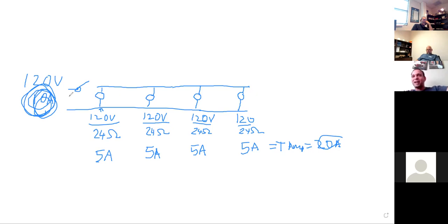I guess we can conclude that it's the generator that provides the overload, right? It doesn't provide overload. If you took the breaker out of the generator, you'd just roast the generator. You've got to put a breaker in. Generators have breakers. If the breaker is rated at 10 amps and you're applying 20 amps to it, the breaker is going to open, just like it does in a substation.